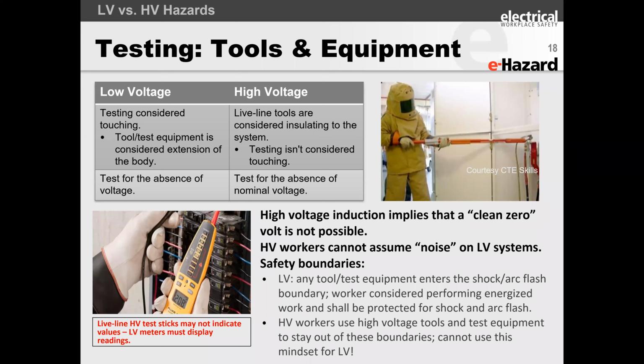Here's another important thing. At low voltage, what do we want to test for? We want to test for 0 volts. At high voltage, we hardly ever test for 0 volts. Instead, we want to test for the absence of nominal voltage. For example, if it's a 13.8 kV system or 115,000 volts, we're not testing for 0 volts, we're making sure that 13.8 kV or 115 kV is not present.